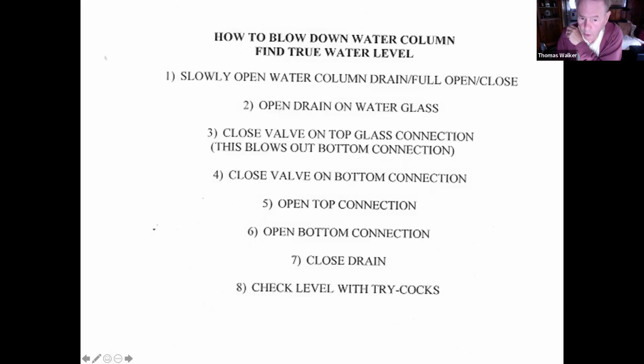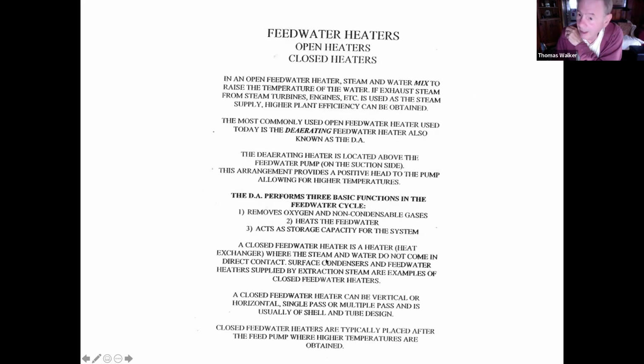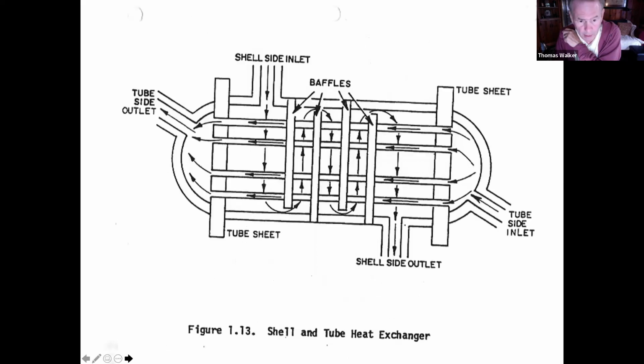A closed feed water heater is a heat exchanger in which the water and steam do not come in direct contact. The most common example of that is what you and I know as a shell and tube heat exchanger. In the typical arrangement, the water is inside the tubes. The steam is outside the tubes on the shell side. And the steam, through a series of baffles, comes in contact with those tubes and gives up its heat to the water. We've been heating water this way for about 200 years. So this is not a new idea.